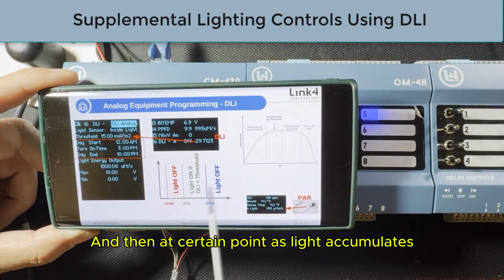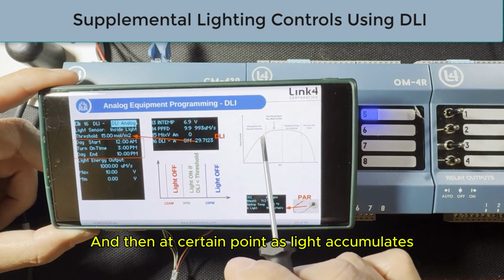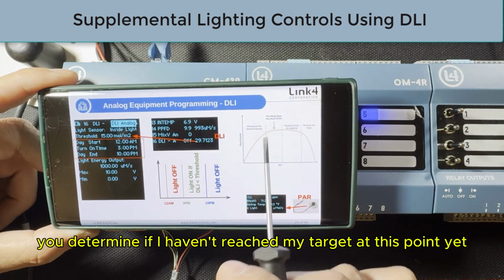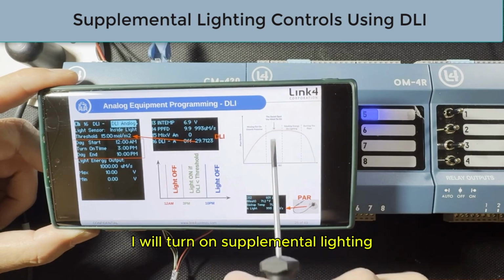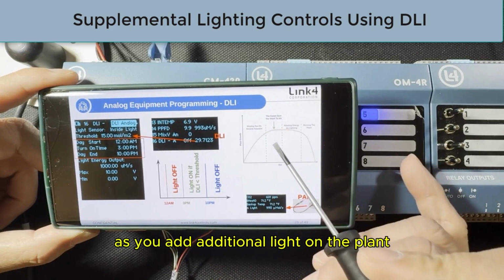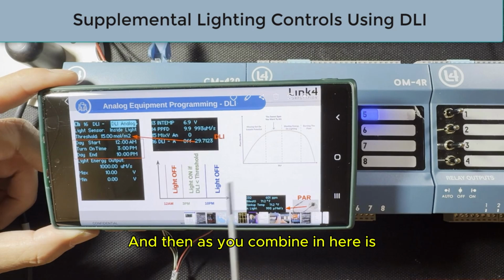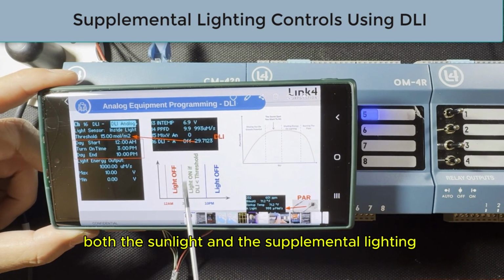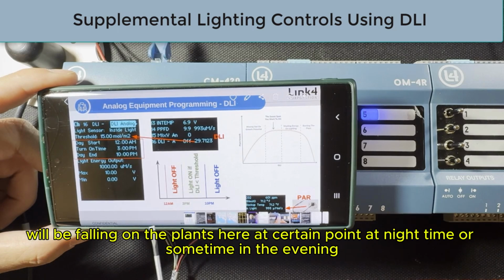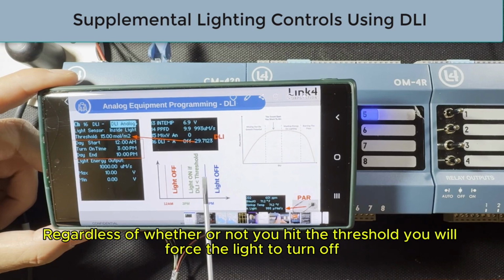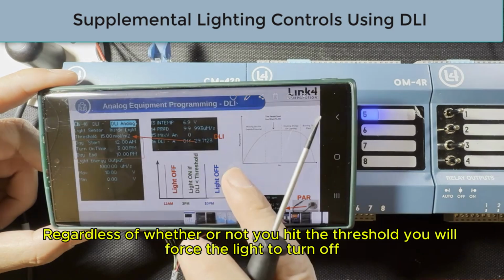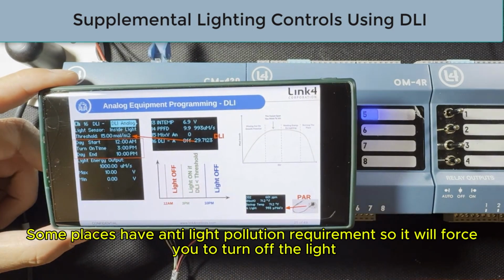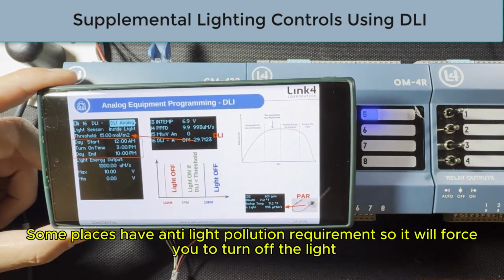And then at a certain point, as light accumulates, you determine: if I haven't reached my target at this point yet, I will turn on supplemental lighting to add additional light on the plant. Combined in here is both the sunlight and the supplemental lighting falling on the plants. At a certain point at nighttime or sometime in the evening, regardless of whether or not you hit the threshold, you will force the light to turn off. Some places have anti-light pollution requirements, so it forces you to turn off the light.